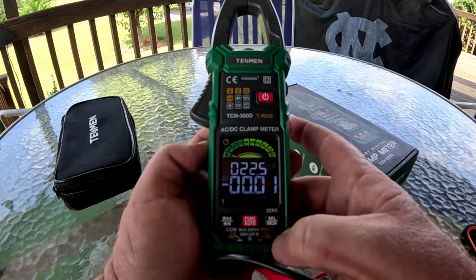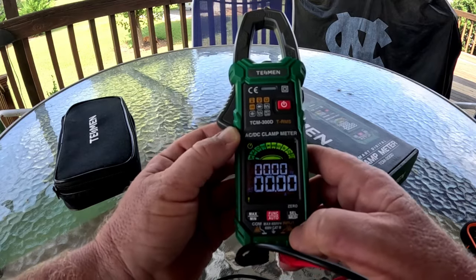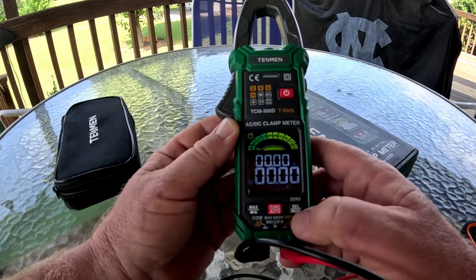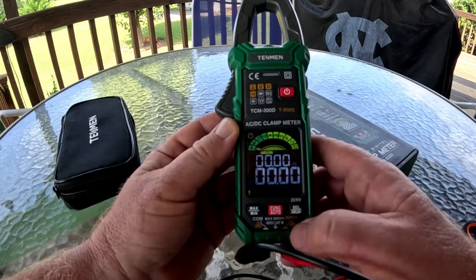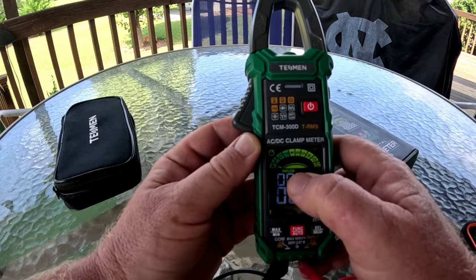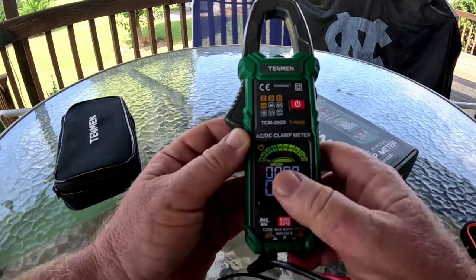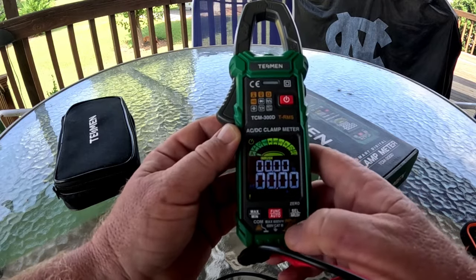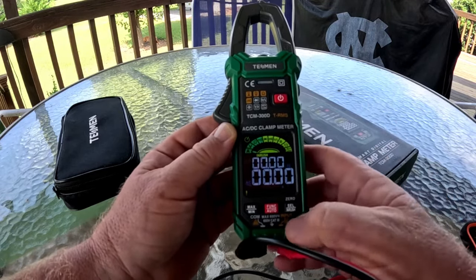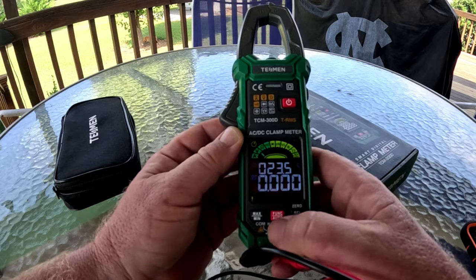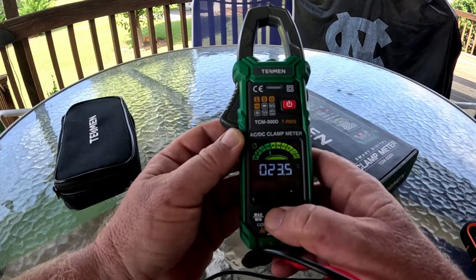We'll go to amps real quick, select AC amps, and then hit the button again. You see it says inrush there. We'll test that, but it will allow you to check inrush on a compressor or a motor when it starts, things like that. We'll come back out of that, and then pretty simple.